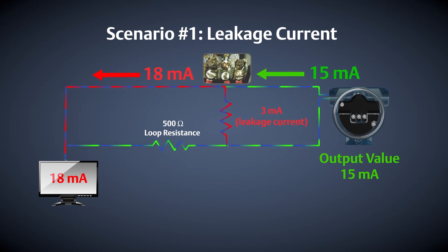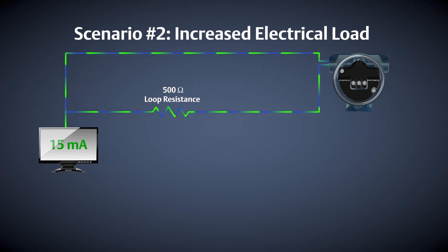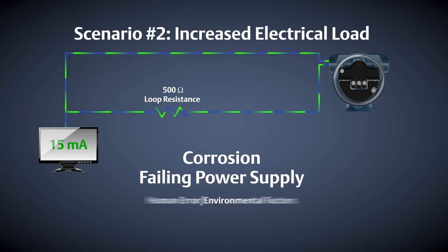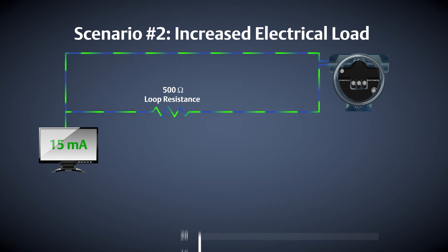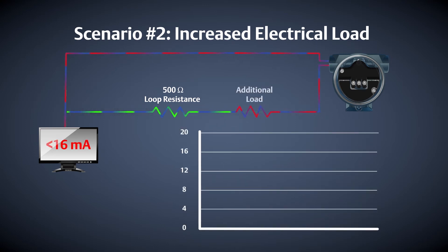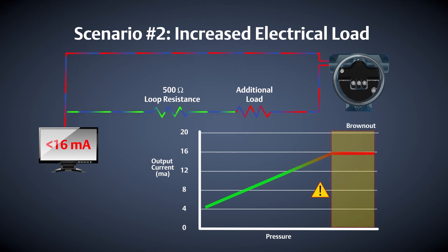The second scenario is an increase in the electrical load of the wiring loop. This can be caused by corrosion, a failing power supply, human error, or other environmental factors. In this scenario, the electrical loop was designed to have 500 ohms of resistance. When additional resistance is inadvertently added to the control loop, the reliability of the control loop is compromised. With an increased wiring loop resistance, there may not be enough voltage for the transmitter to drive the loop to the proper milliamp value or even to an alarm state.